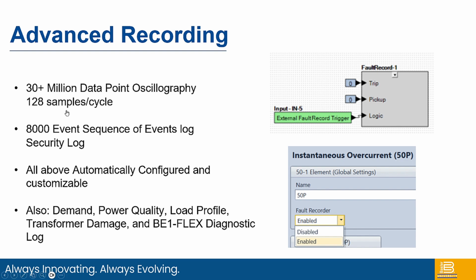In addition to the fault capture, so that's the oscillography, we can do sequence of events, and that log is enabled by default automatically. 8,000 events. It's going to record the first in, first out sequence of any digital transition in the device. So if an element picks up, if somebody logs in, any sort of condition like that is going to record it in the sequence of events.